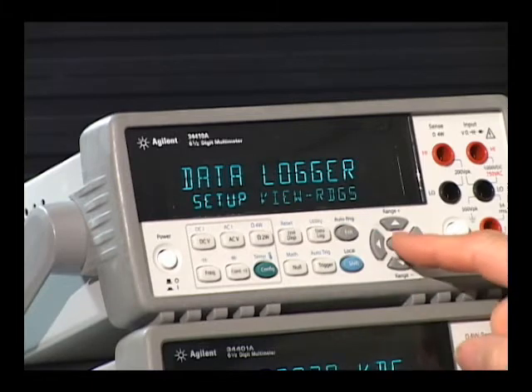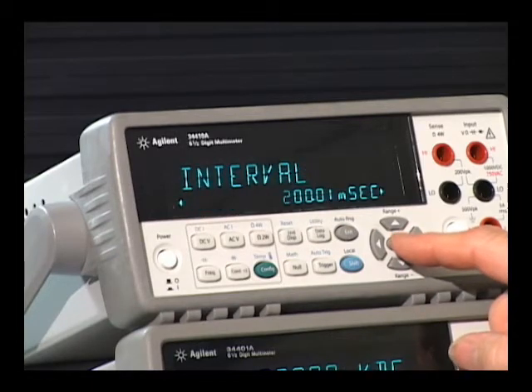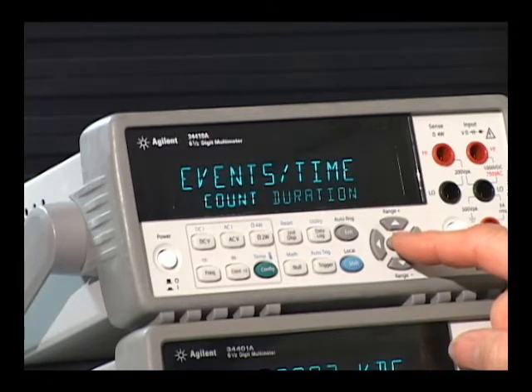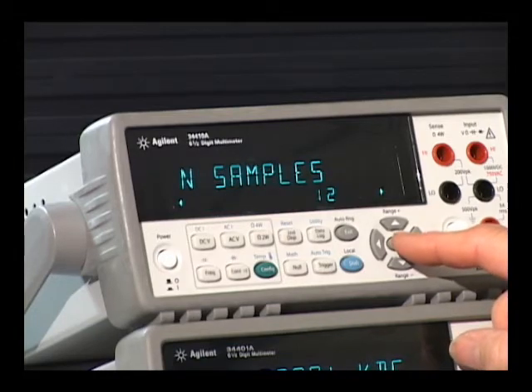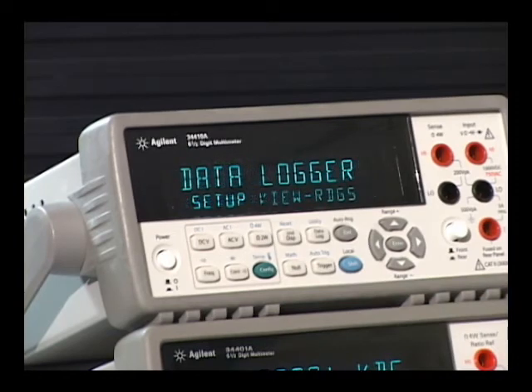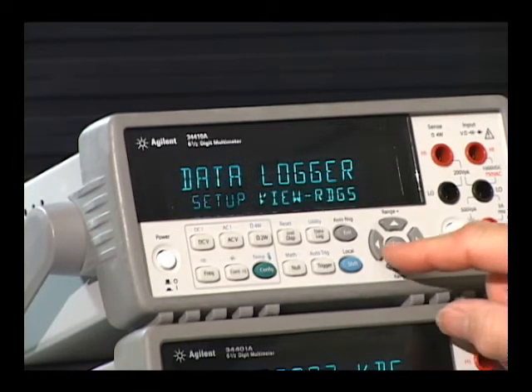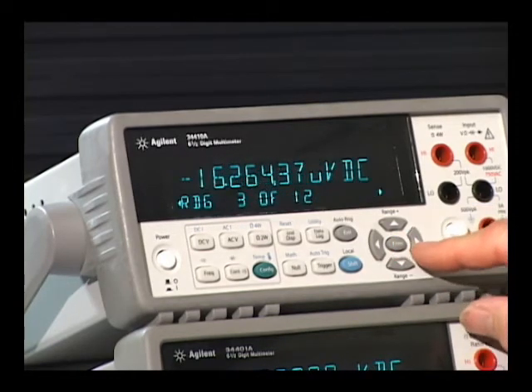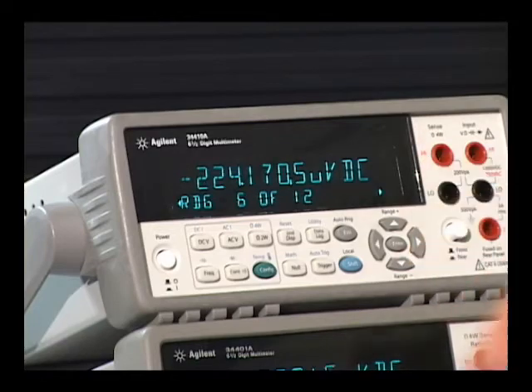As you can see, you can walk through the menu, set up a delay time, sample time, how many counts—in this case I've set it up for 12. I press trigger and it takes the measurements. Now I can view the readings that I just took, and I can store up to 50,000 readings in the 34410A.